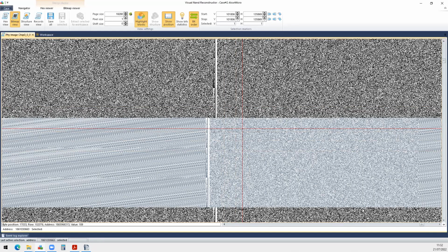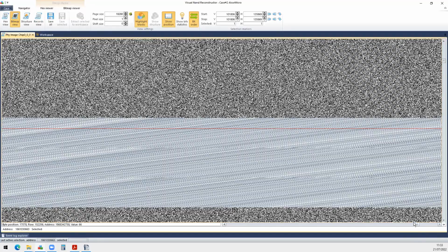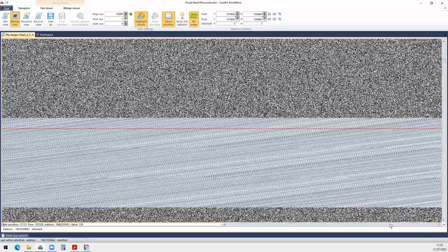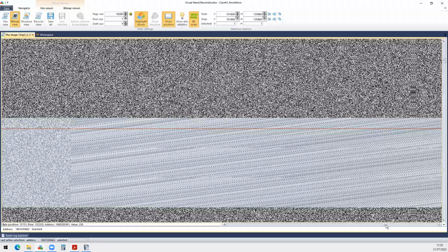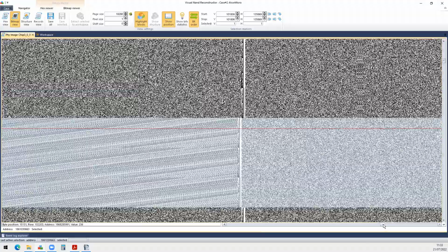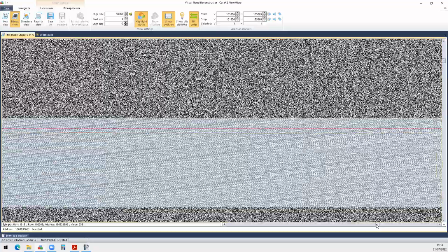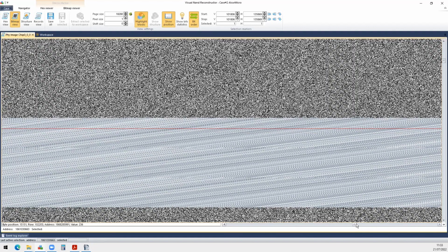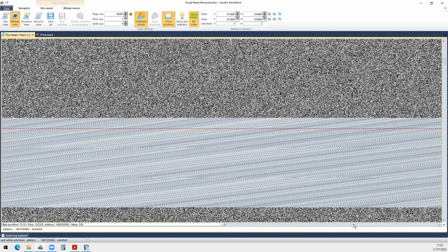In the case of Alcor microcontrollers, we call these bad columns XORed bad columns, and you won't be able to notice them through the bitmap. If you scroll here horizontally, maybe you will find some distortions. However, the first time you have such a case, you won't actually be able to see any differences. So to determine whether we have these bad columns or not, we can also check the service area.